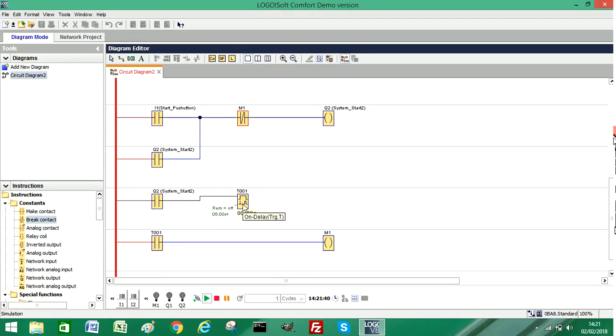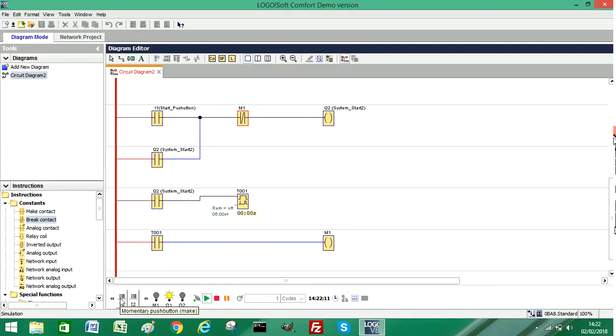We will manually start it, the timer will expire after five seconds and trigger our memory bit which will automatically stop our system. I'm going to press our first input for the start push button. You can see Q2 is on, the timer is counting - three seconds, four seconds, five seconds - and now you can see Q2 has gone off, the system has stopped. So to run through that again: press the start push button, the system is latched, the timer starts, once the timer expires the system switches off, Q2 goes off. This is how you create an automatic stop sequence in ladder logic.